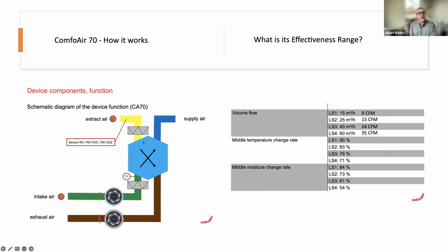At the bottom range is the middle moisture exchange rate. So it's pretty good at the lower speed. It's 84% effective at enthalpy recovery, right? So we're managing the moisture in there. And one of the key things in this case, you kind of go through a debate. If you want the best energy recovery in a building, you use an HRV because they're generally just more efficient. But every HRV needs a condensate drain, because when it's cold outside, the warm wet air comes back from the kitchen and bath, chills in the heat exchange area, turns into condensate, and we've got to provide a drain out. In existing buildings, providing condensate drains and draining that away can be a challenge. So it's a nice thing to have an ERV that doesn't need a condensate drain, and we can just install it in the side of the building, and away we go.